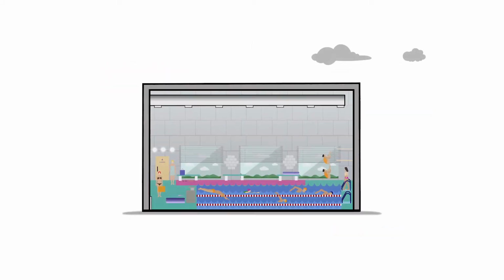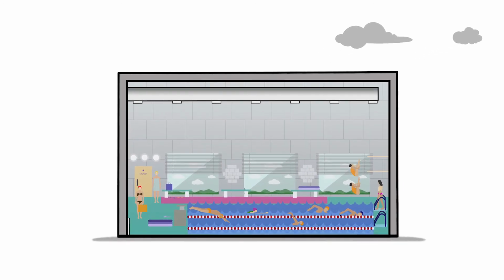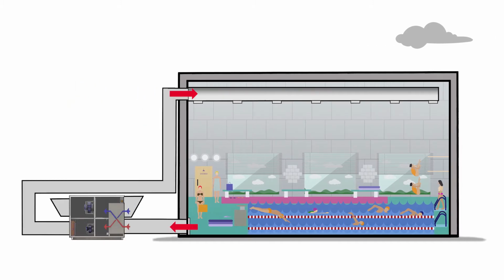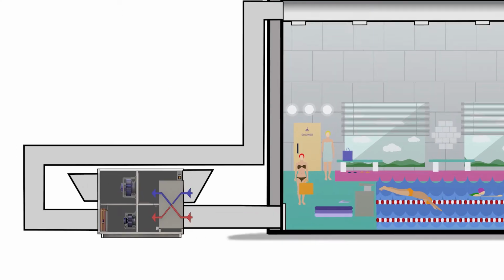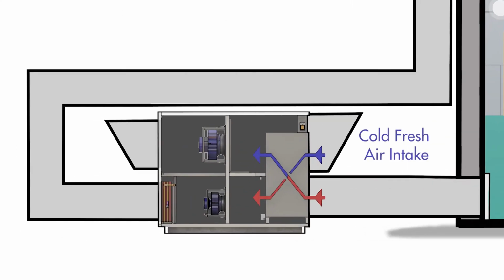So to start with, let's go over a conventional indoor pool facility. As indoor pools require large amounts of ventilation to manage humidity and airborne chloramine levels, it is common to use heat recovery ventilators to exchange heat between the air being exhausted outside and the incoming fresh air. This minimises the energy penalty of introducing fresh outside air that is too hot or too cold.